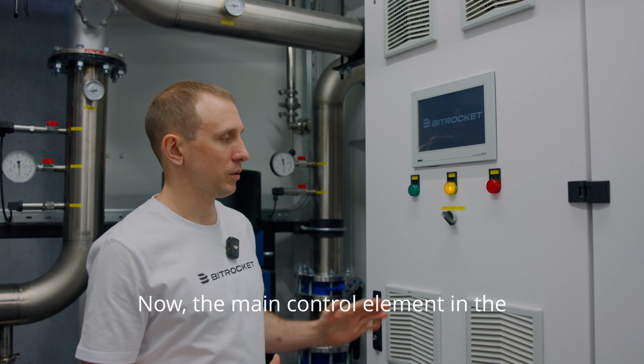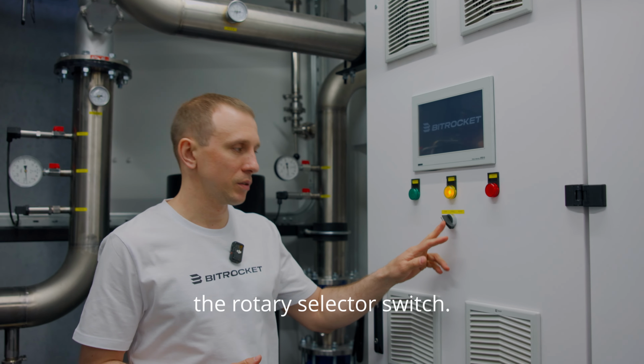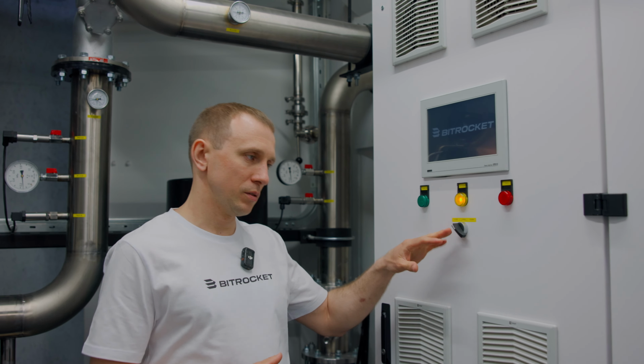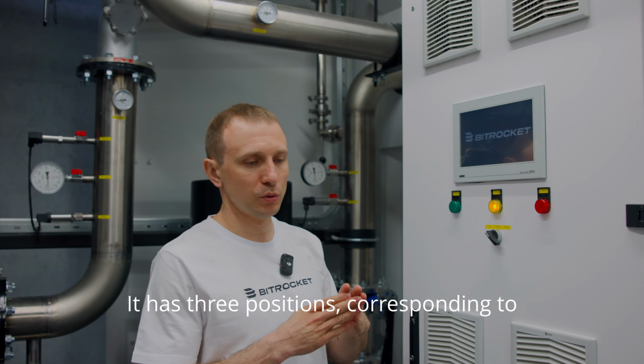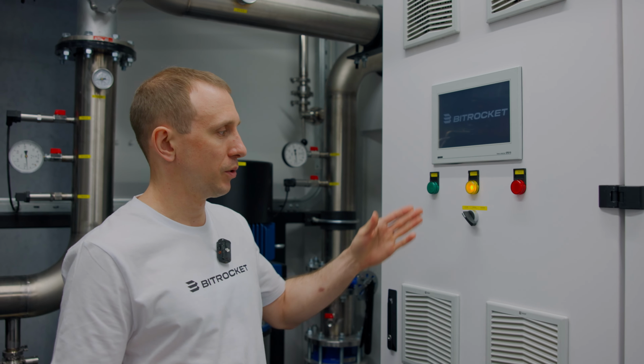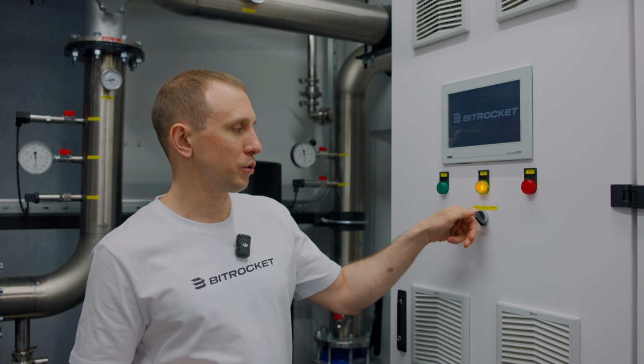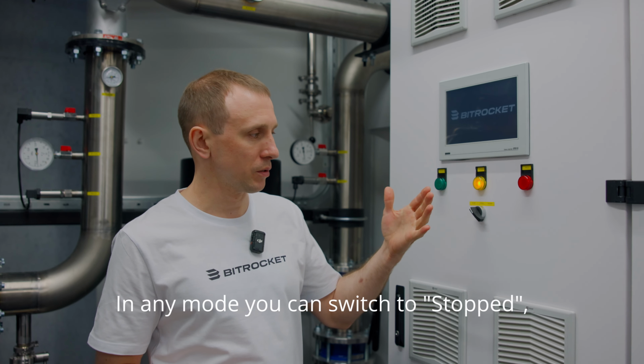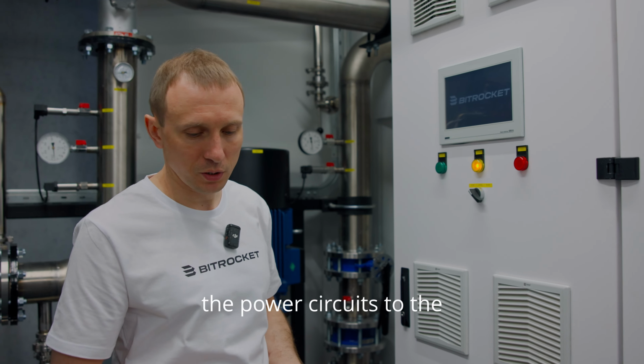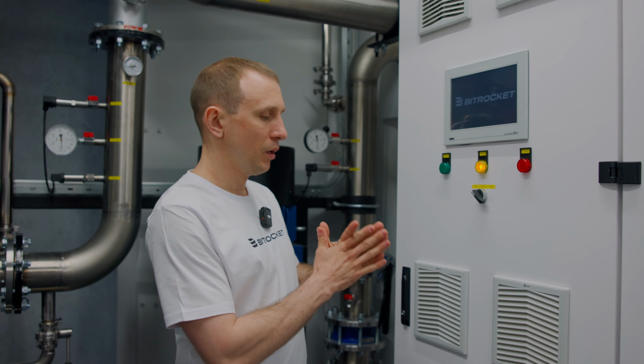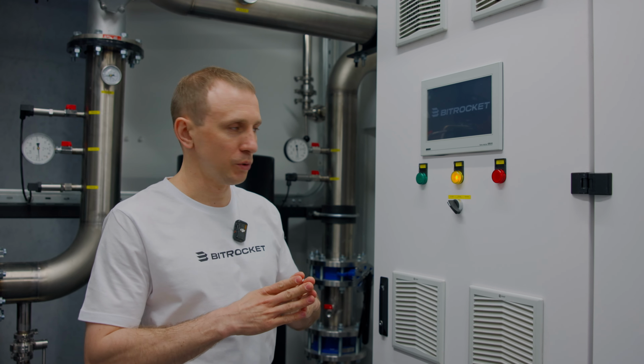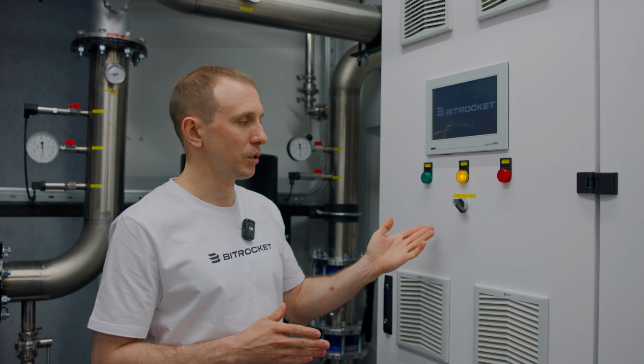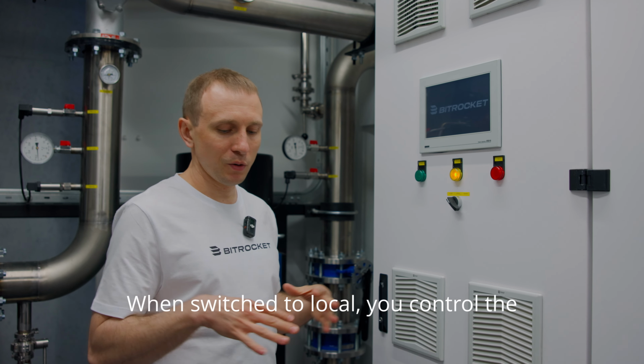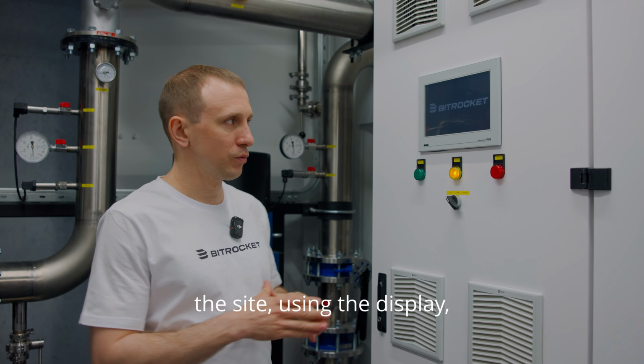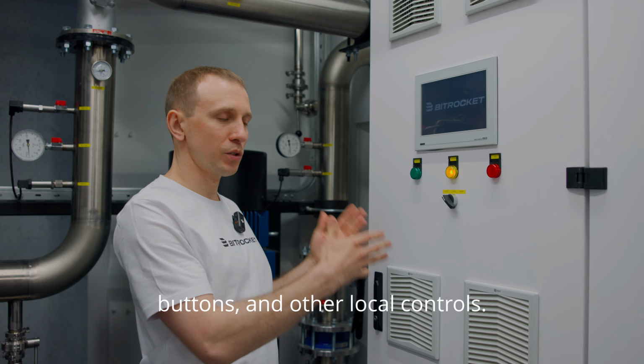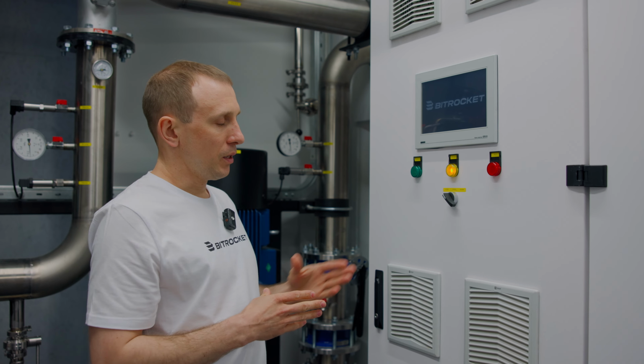Now, the main control element in the automation cabinet is the rotary selector switch. It has 3 positions, corresponding to 3 main operating modes. The first one is stopped. In any mode, you can switch to stopped, which immediately breaks the power circuits to the frequency drives, shutting everything down. The second position is local mode. When switched to local, you control the container directly from the site, using the display, buttons, and other local controls.